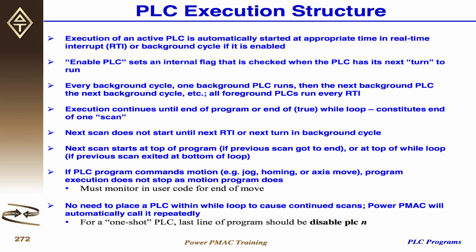The real-time interrupt PLCs will actually all run every real-time interrupt. So if you have, for example, PLCs 0 through 3 enabled to run in foreground, all of them will run in order every real-time interrupt.